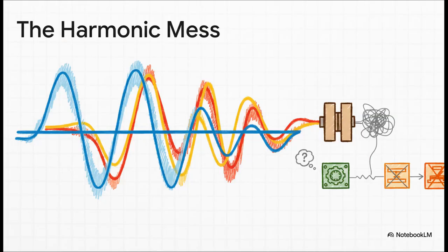And this distortion creates what engineers call a harmonic mess. That current waveform becomes all peaky and spiky, and it's suddenly full of these unwanted garbage frequencies, the odd harmonics. The transformer just loses all its good transformer behavior. And this is critically dangerous for the little instrument transformers, the CTs and VTs, that our grid protection systems rely on. If they saturate, they can't measure a fault correctly, which might mean a circuit breaker doesn't trip when it absolutely needs to.